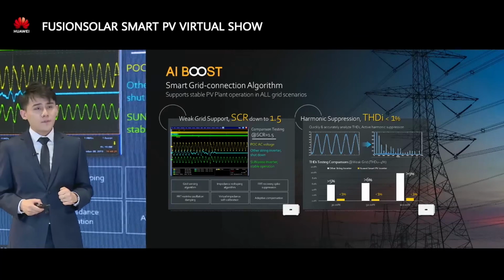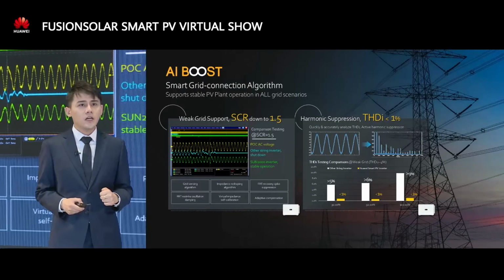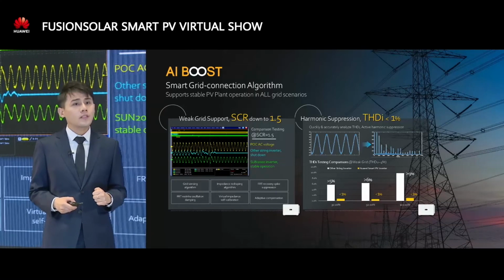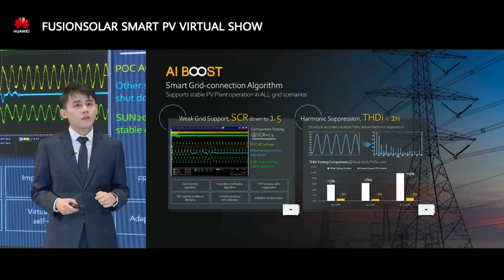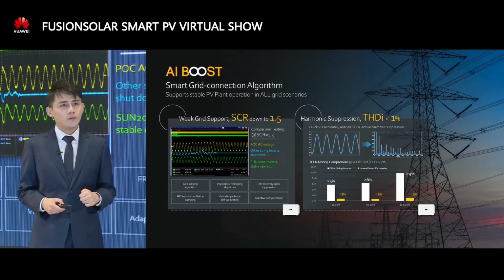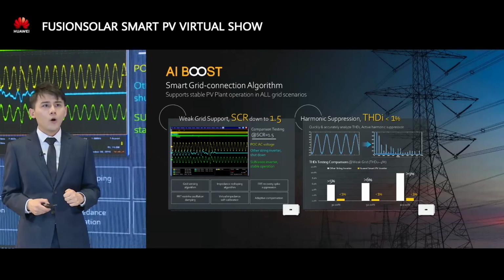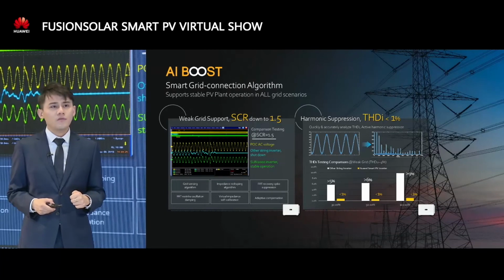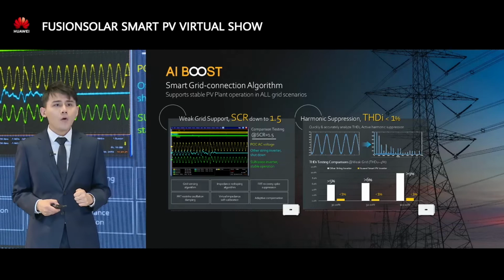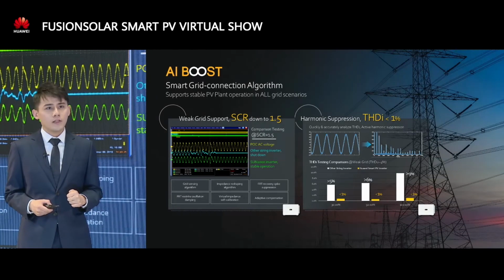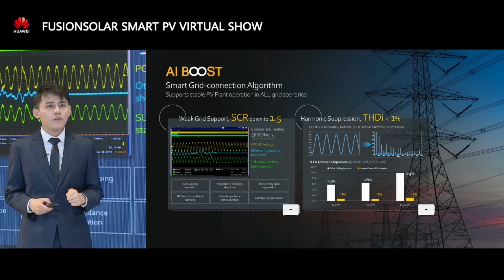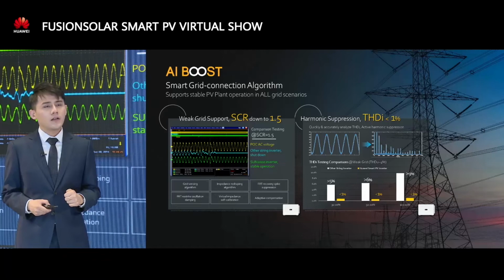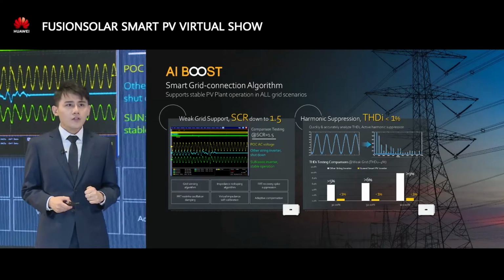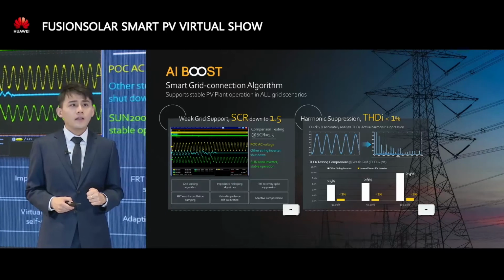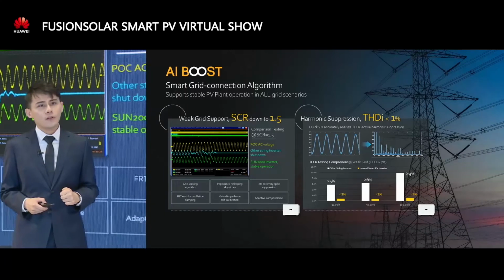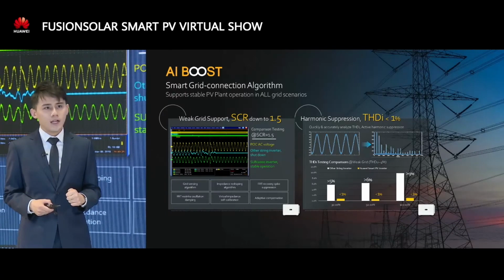And here are some testing curves. In the weak grid connection testing, the output waveform of Huawei inverters is still stable when SCR is 1.5. However, the output waveform of other string inverters is distorted when SCR is 3. The inverters can work only with reduced power or switch to shutdown for self-protection. In terms of power quality, in a real power grid with background harmonics, when THDU is about 4%, Huawei inverters ensure the THDI is less than 1%. In comparison, other string inverters can barely achieve the claimed THDI of less than 3% in laboratory conditions. In a real power grid, the harmonics would surge to 9%.